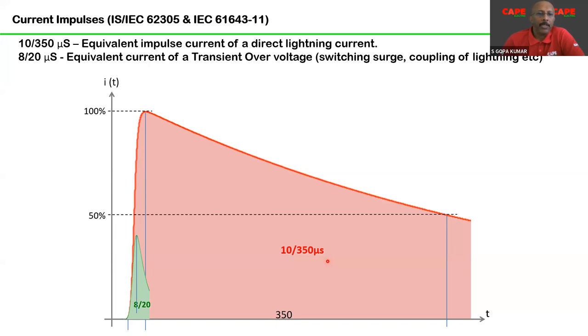Now, the two subjects which you should understand: components of external lightning protection, means you have a building, you have some clamps, clips, conductors. Those need to be tested with the 10 by 350 microseconds wave shape. And the smaller devices such as SPDs, sometimes 10 by 350 microseconds, which is called a type 1 SPD. Sometimes the SPDs are tested with 8 by 20 microseconds, which is called a type 2 SPD. So basically there are two energy wave shapes.